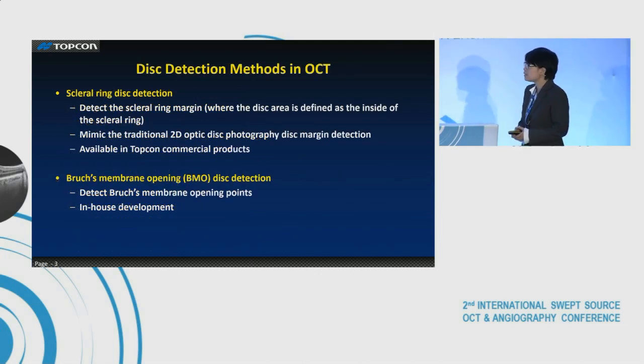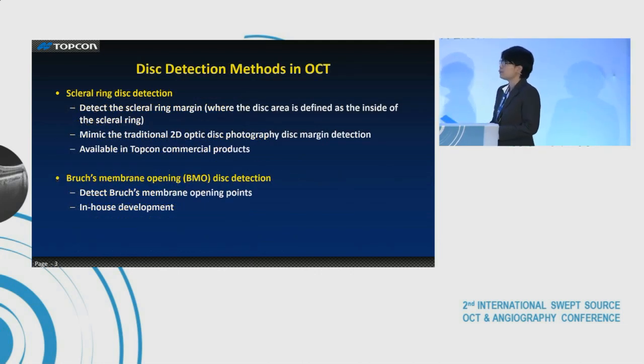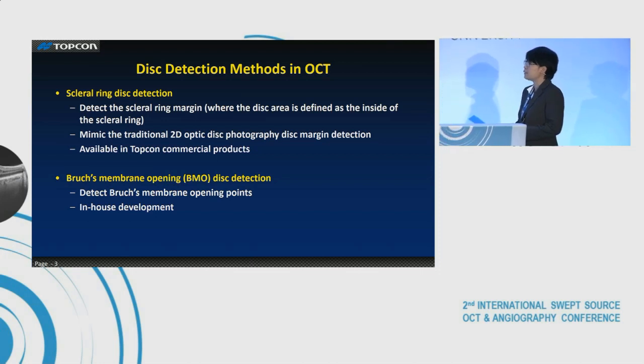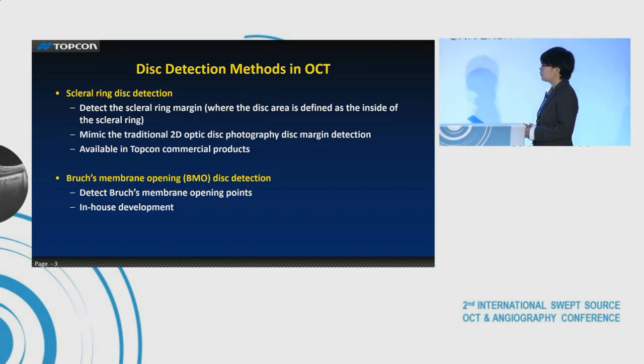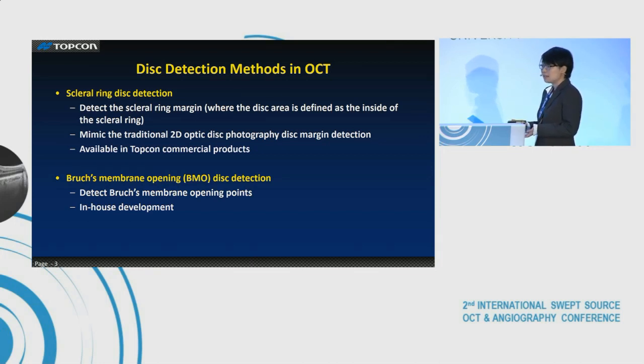To begin with, I want to briefly introduce the disk detection methods in OCT. The first one is scleral ring disk detection. It is to detect the scleral ring margin, where the disk area is defined as the inside of the scleral ring. This method was originally developed to mimic the traditional 2D optic disk photography disk margin detection. It is widely available in Topcon commercial OCT products like Trident, Maestro, Atlantis, et cetera.